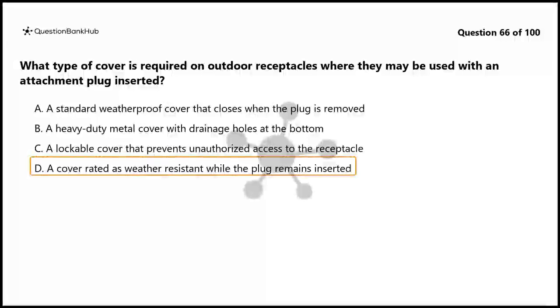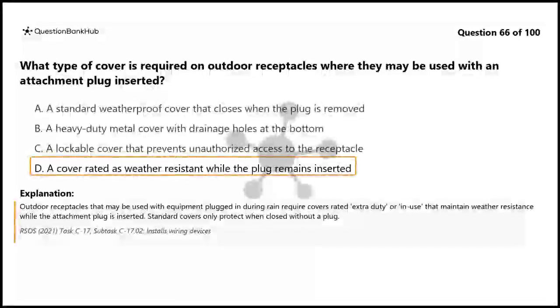The correct answer is D. A cover rated as weather-resistant while the plug remains inserted. Outdoor receptacles that may be used with equipment plugged in during rain require covers rated extra duty or in use that maintain weather resistance while the attachment plug is inserted. Standard covers only protect when closed without a plug.